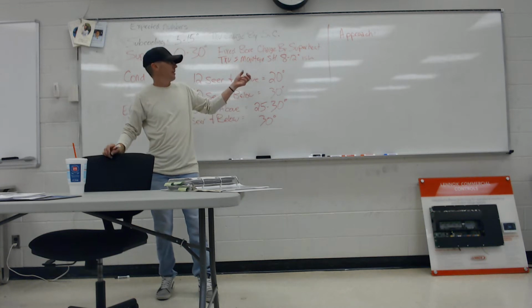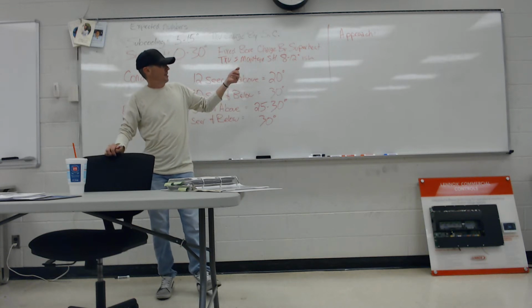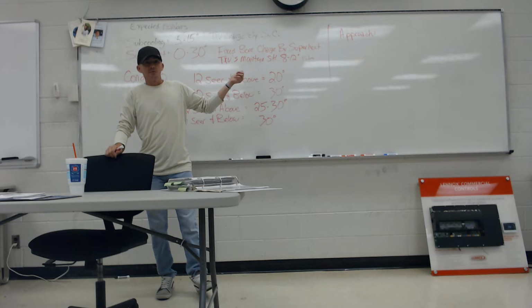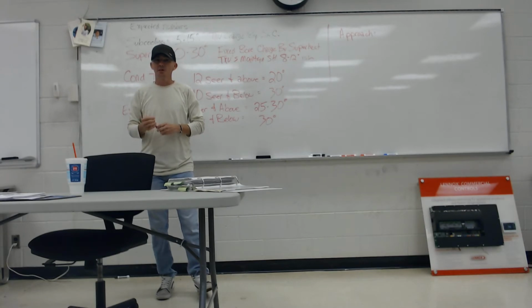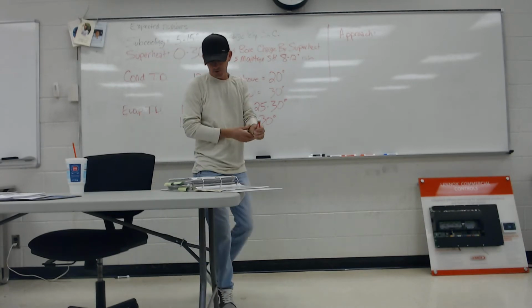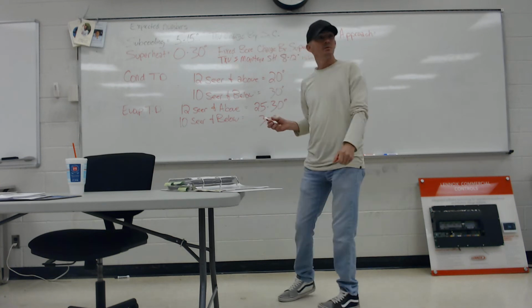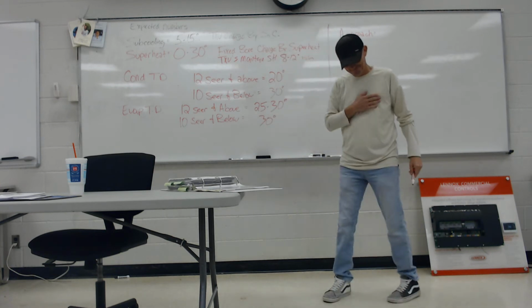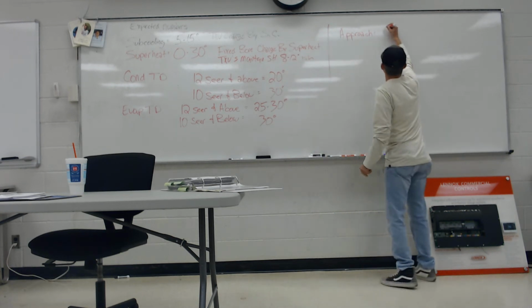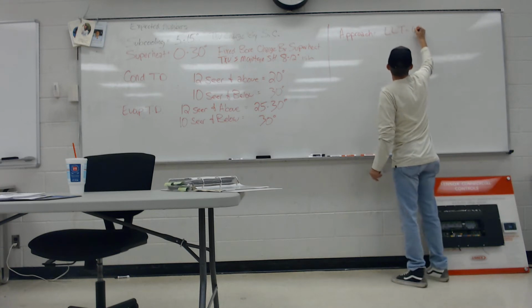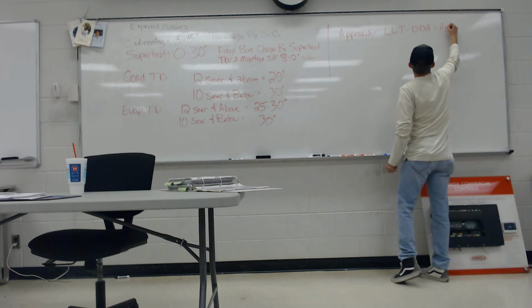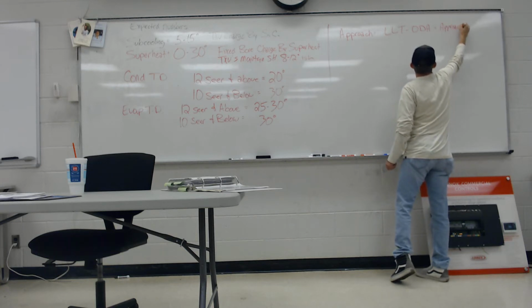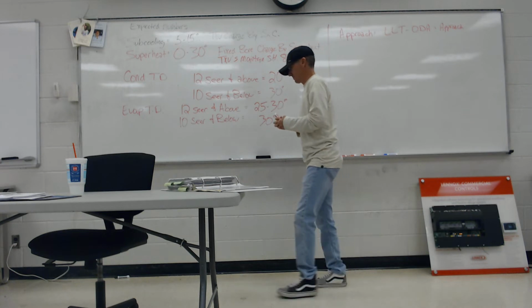Approach is used on air-to-air, DX, direct expansion, air-cooled stuff. Approach is for TXV units, so it's kind of like subcooling. Anyone happen to know the formula for this? Liquid line temp minus outdoor air temp.